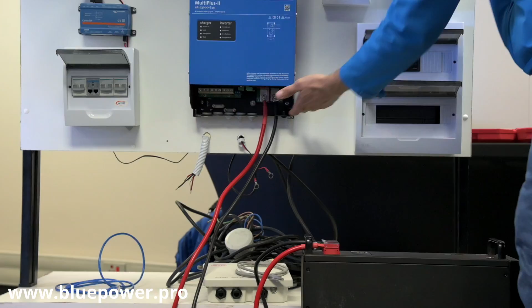And you just torque it over there, torque it over here. All that's good. So you make sure our inverter is switched off, and then the procedure would usually be to start up your battery. As soon as the battery is started up, do your measurements, double check, and then triple check. Then you close your fuses, and then you double check and triple check, and then you can switch your inverter on. Check if that's got power over there. It's not going to switch on.